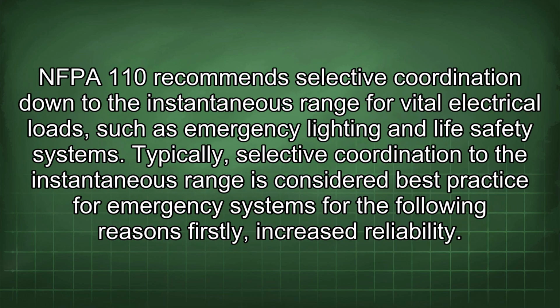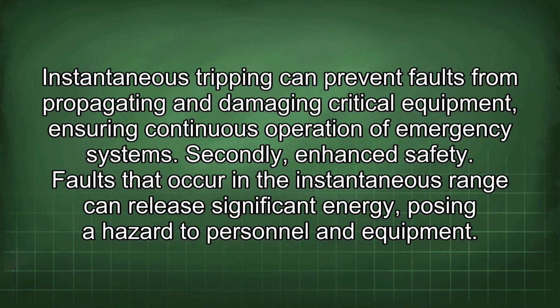NFPA 110 recommends selective coordination down to the instantaneous range for vital electrical loads such as emergency lighting and life safety systems. Typically, selective coordination to the instantaneous range is considered best practice for emergency systems for the following reasons. Firstly, increased reliability. Instantaneous tripping can prevent faults from propagating and damaging critical equipment, ensuring continuous operation of emergency systems.